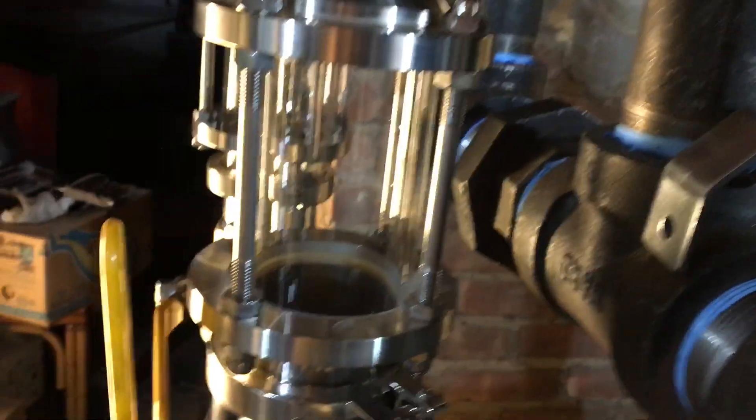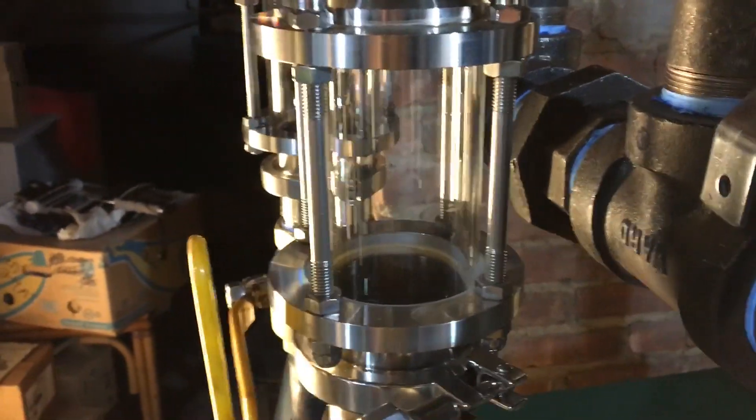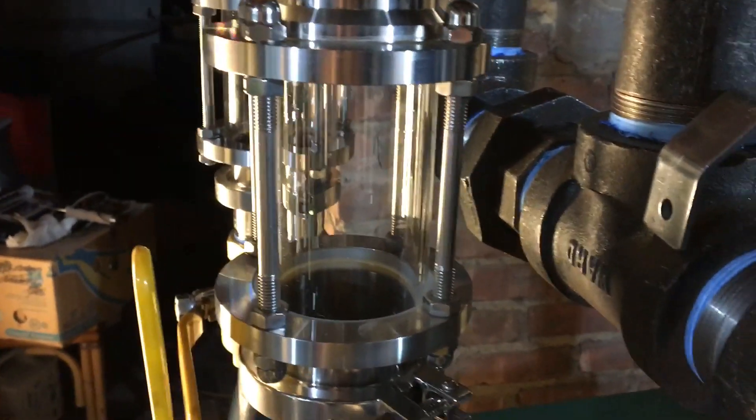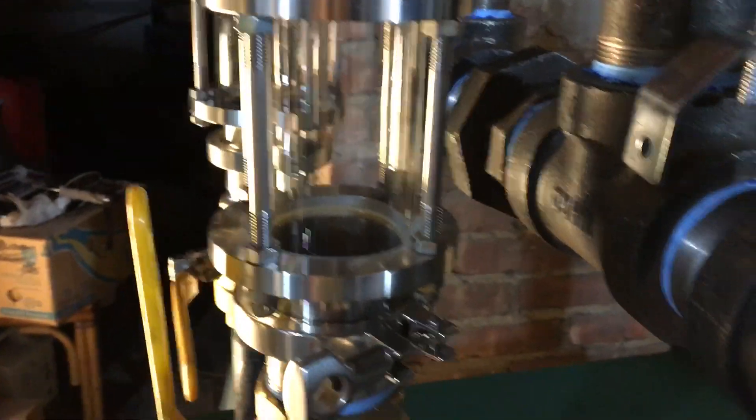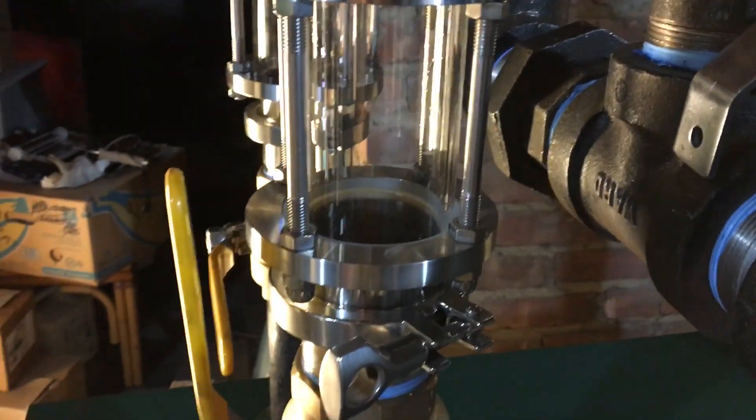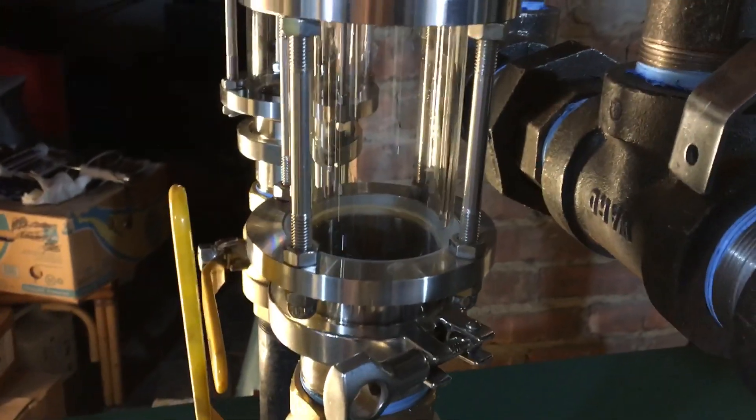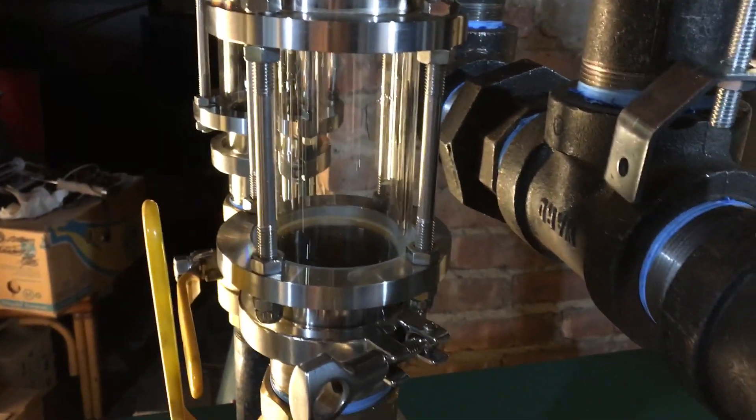I mean that's another two feet there, and I think that even with the manufacturer's requirement of a non-drop header, a traditional standard header, and with the water level at the specified amount, there's just not going to be any water getting thrown into the main, not even close.